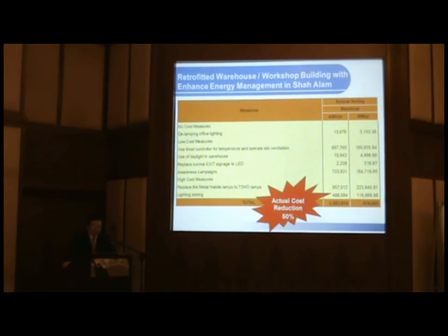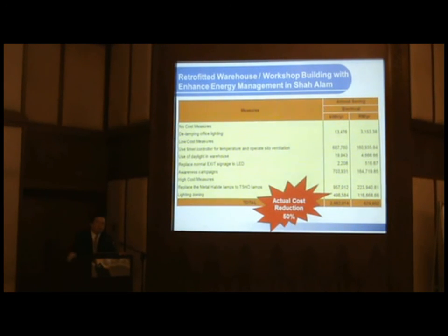But during the energy audit, we found the fan running 24 hours. At night it's cooler, but the fan was still running. So they invested in a temperature sensor set to about 28 degrees. When night time temperatures drop, or during the rainy season, it will automatically turn off the fan.